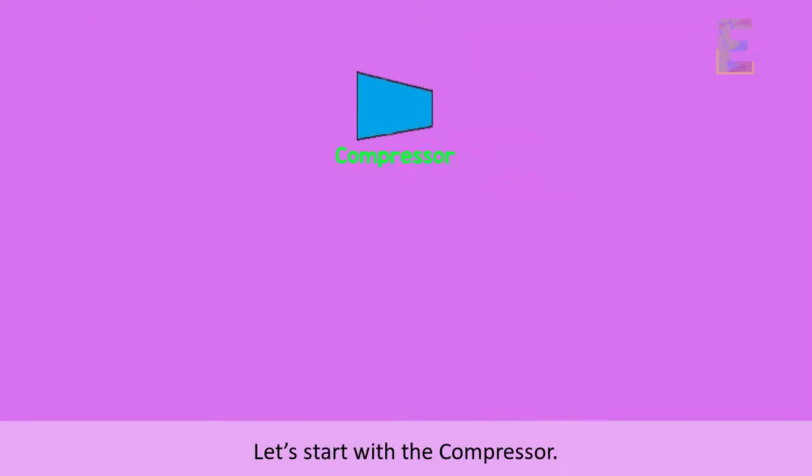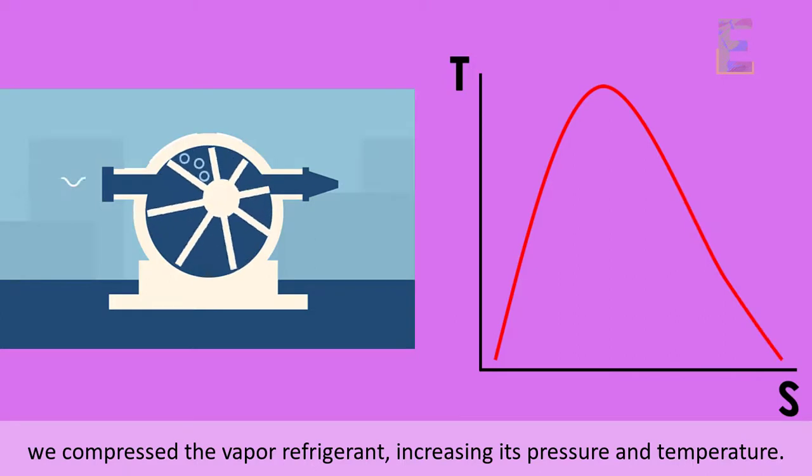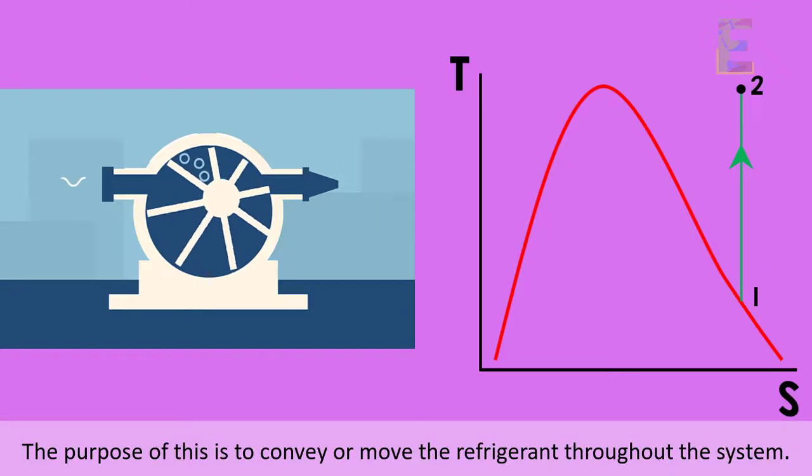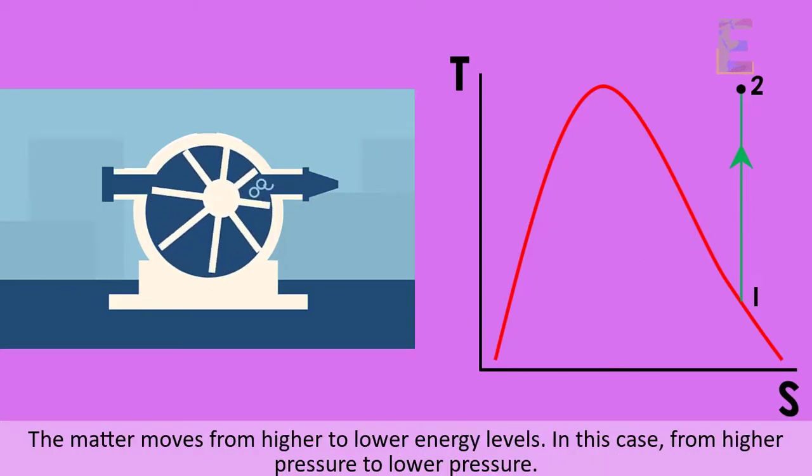Let's start with the compressor. Here at the compressor, we compress the vapor refrigerant, increasing its pressure and temperature. The purpose of this is to convey or move the refrigerant throughout the system. As we all know, by the second law of thermodynamics, in order for particles or matter to move, we need a difference in energy level. The matter moves from higher to lower energy levels. In this case, from higher pressure to lower pressure.